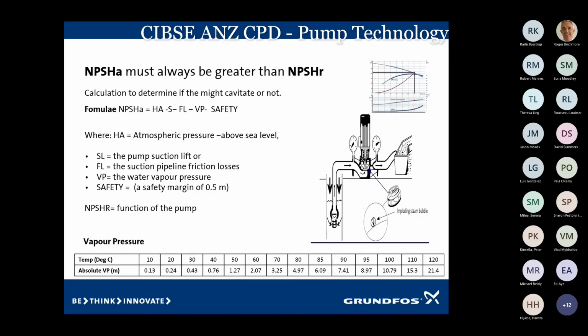So where the red dot is, our flow rate is 70 cubic meters an hour on the pump curve. If I drop my eye straight down, I hit the net positive suction head curve, and that tells me that the requirement is 3 meters. So at that duty point, my net positive suction head required is 3 meters.